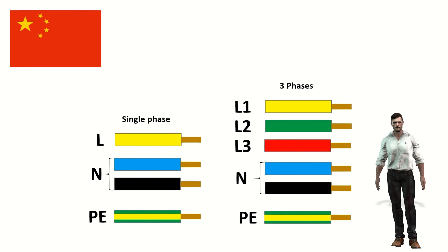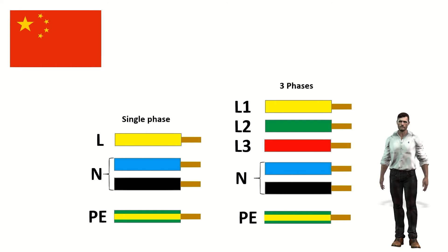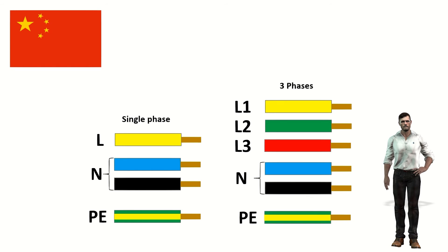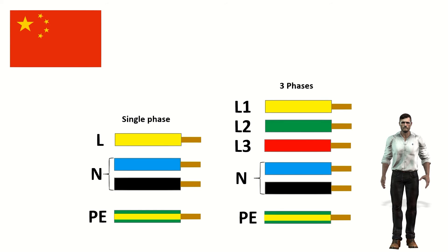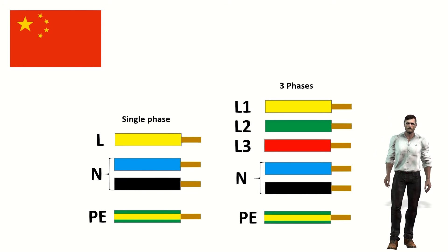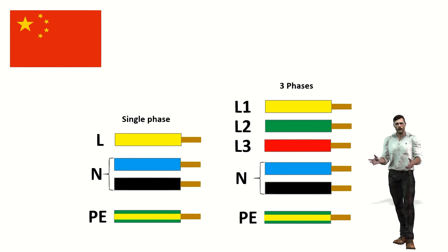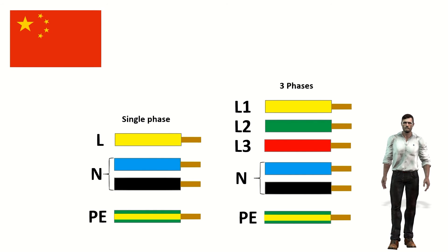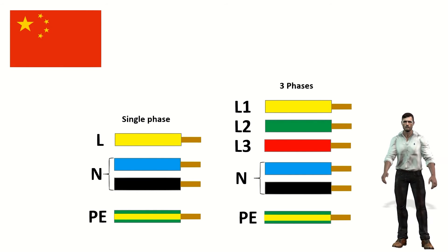China has its own color code. For single-phase systems, the phase cable (L) uses the color yellow, and for the neutral cable (N), the color light blue or black is used. The earth or protection wire (PE) will be green and yellow. For a three-phase AC system: phase 1 (L1) is yellow, phase 2 (L2) is green, and phase 3 (L3) is red. The neutral (N) can be blue or black, and for the earth or protection wire (PE), green with a yellow line is used.